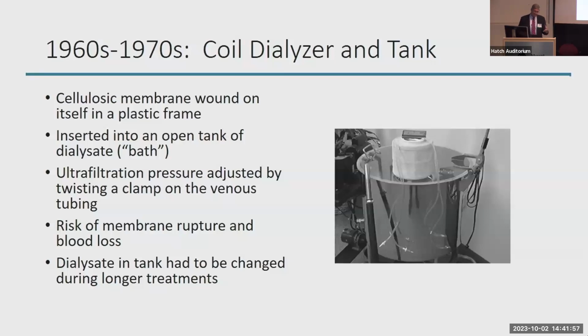What was crude in retrospect, it's almost horrifying that we did it this way, was because this was an open system, it wasn't a single pass system that we have now, there was no way to manipulate the transmembrane pressure except manually by inserting a clamp over the venous return line. So what you did is you increased the pressure within the membrane, and that allowed for a greater transmembrane pressure for greater ultrafiltration. The problem is that you had this loose baggie sitting inside a plastic frame, and if you were a little more exuberant than you should have been in terms of increasing the venous pressure, the whole system exploded. Okay, and this was not unknown that patients who were being treated with these coil dialyzers could have an accident with an explosion.